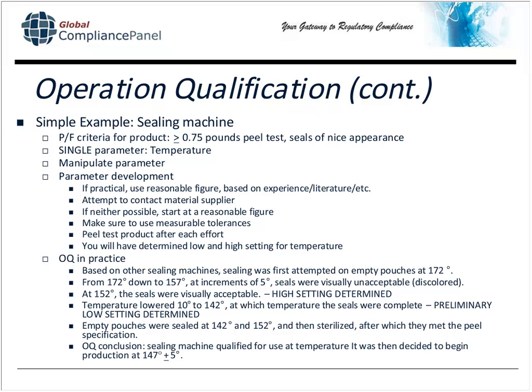You're going to end up hitting your high and low cliffs anyway, but if you can have a good starting point, it reduces the time of this OQ. If neither one is possible, if the supplier won't help you and you can't find any sort of literature and you have no experience, quite honestly, just start somewhere that seems reasonable. And you want to make sure that when you use tolerances, you make them measurable. So from a measurable perspective, while you may have the capability to measure in quarter degrees, a quarter of a degree, for example, that's not something that you want to do. You don't want to set your tolerances that tight to almost be immeasurable, so to speak.